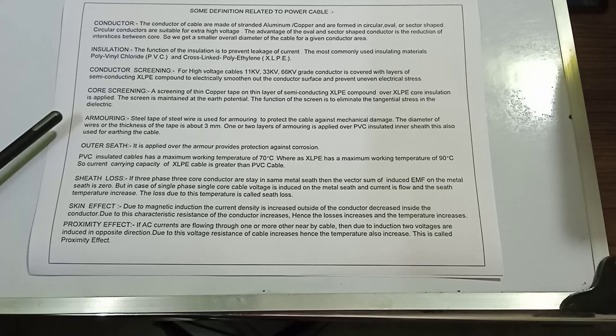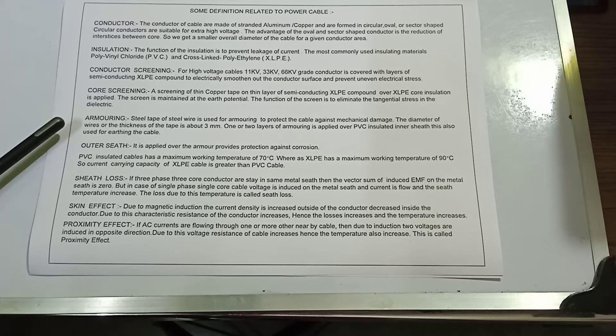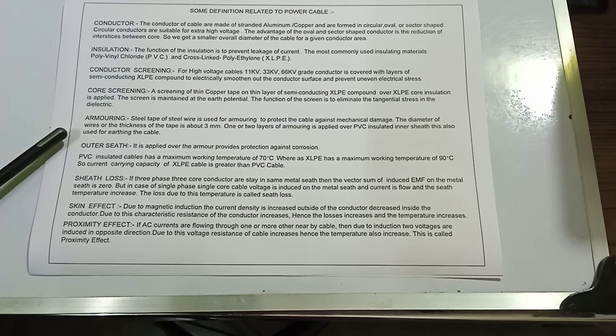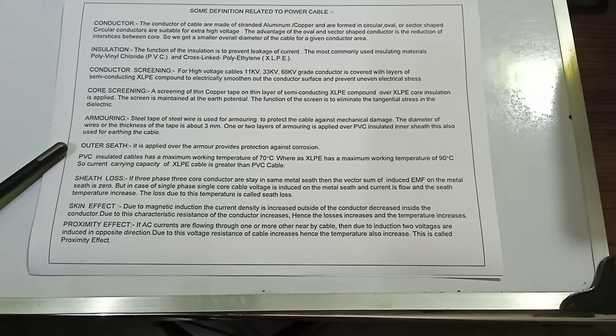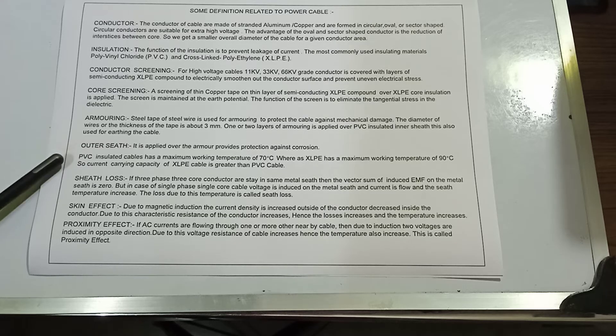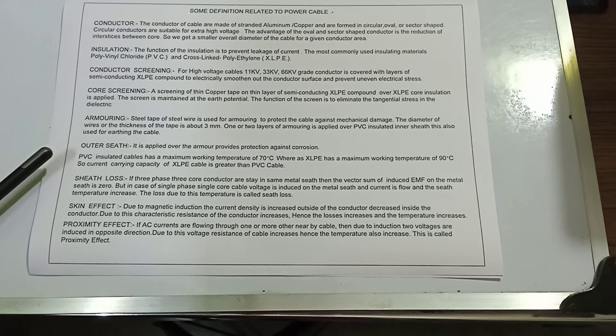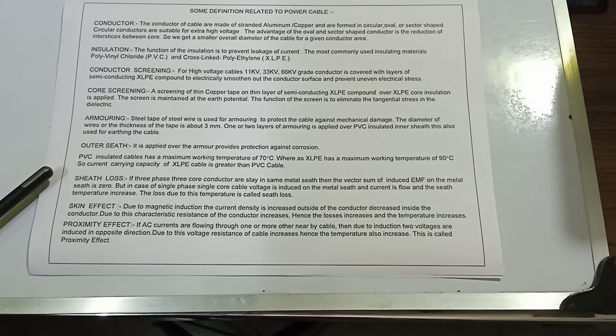The diameter of wires or the thickness of the tape is about 3 mm. One or two layers of armoring are applied over the PVC insulated inner sheath, which is also used for earthing the cable. Next: outer sheath. It is applied over the armor to provide protection against corrosion. PVC insulating cables have a maximum working temperature of 70°C, whereas XLPE has a maximum working temperature of 90°C, so the current carrying capacity of XLPE cable is greater than that of PVC cable.